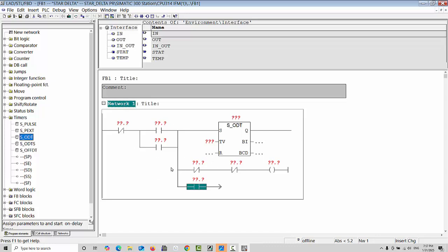You must watch this video carefully. After you completely understand this program, you can design it in your PLC. This contact I am choosing as the timer's close contact, and this one I will choose as the timer's open contact, because when we give supply to this timer, after our supply starts, the first star contactor starts, and when the time is up, this open contact will start our next, the delta contactor.